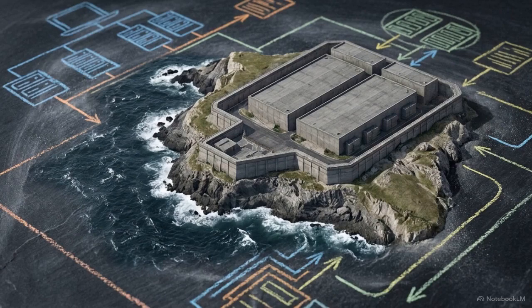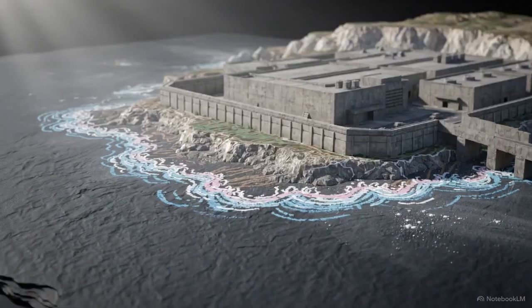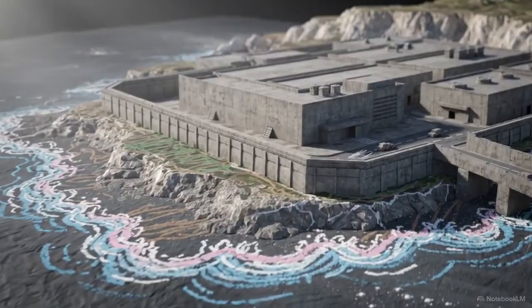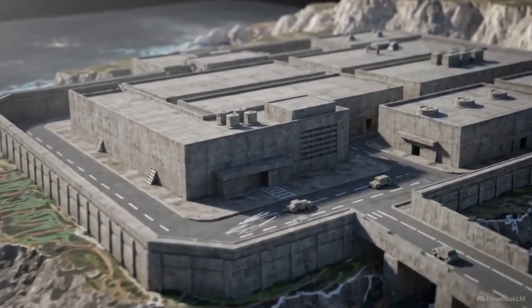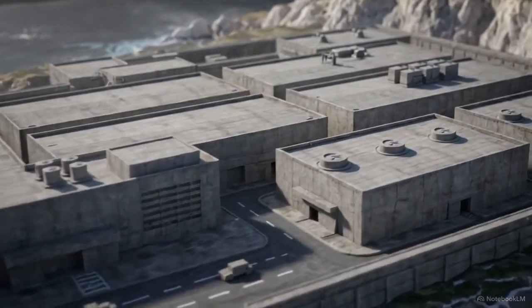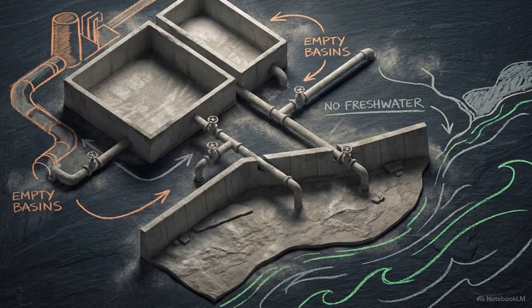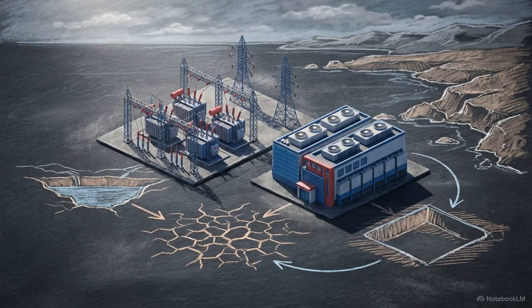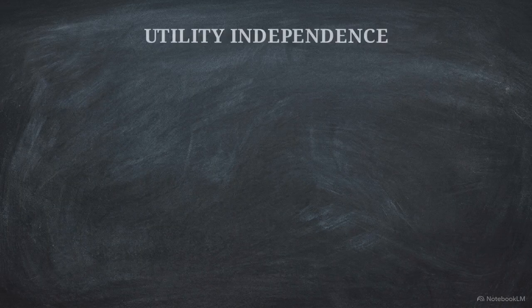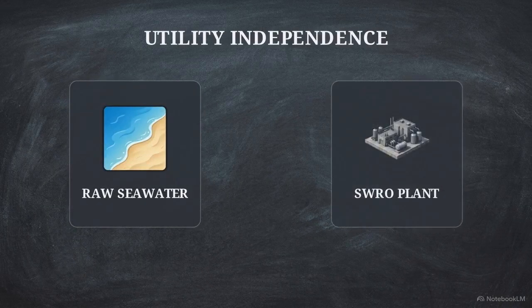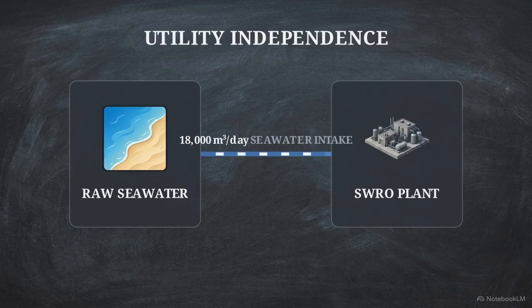Welcome to this advanced engineering training on makeup water supply for high-density liquid-cooled data centers. Our design basis is a coastal campus, representative of a Batam or Nongsa Island environment, scaled to support 144 megawatts of IT load. Building at this scale in a marine environment creates an immediate freshwater constraint. The site provides isolated power generation and strategic regional connectivity, but lacks the municipal reserves required to support traditional or hybrid cooling at scale. To operate independently, the campus must secure its own water supply by engineering a dedicated seawater reverse osmosis, or SWRO, plant on site.